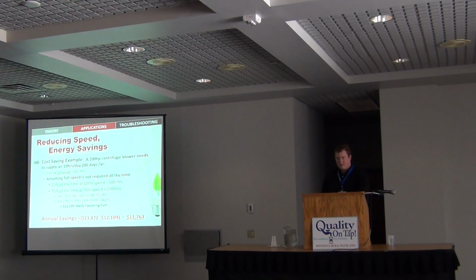essentially saving $11,763 per year. This VFD, in an application where we don't have a pump curve and we're not losing any efficiency by slowing it down, will pay for itself in 3 to 4 years, if the drive costs $30,000 to $40,000. So situations like that can lead to a lot of savings over the life of the drive.